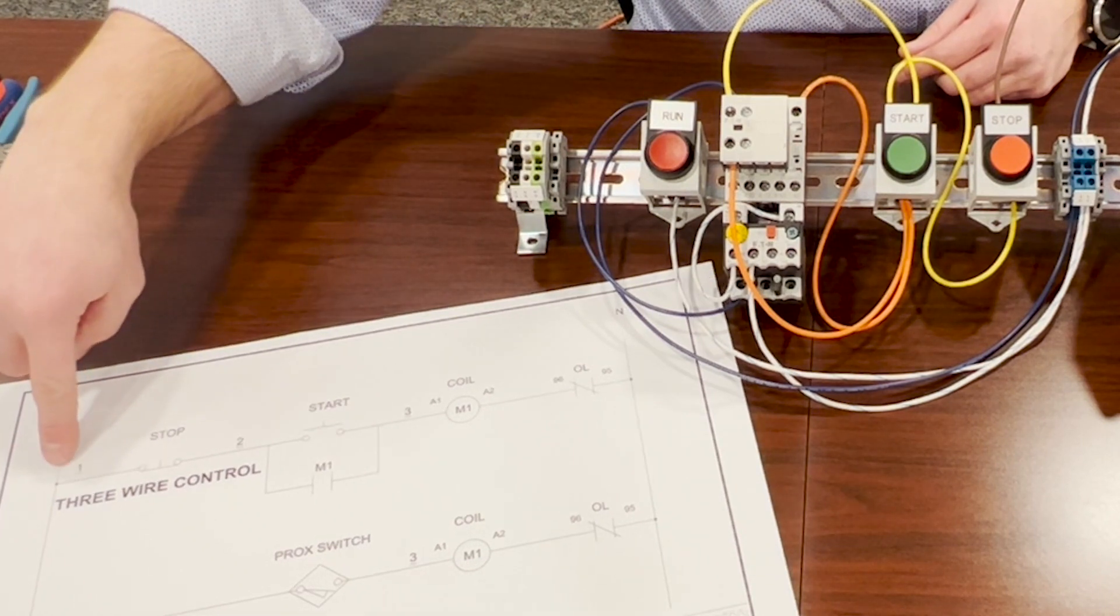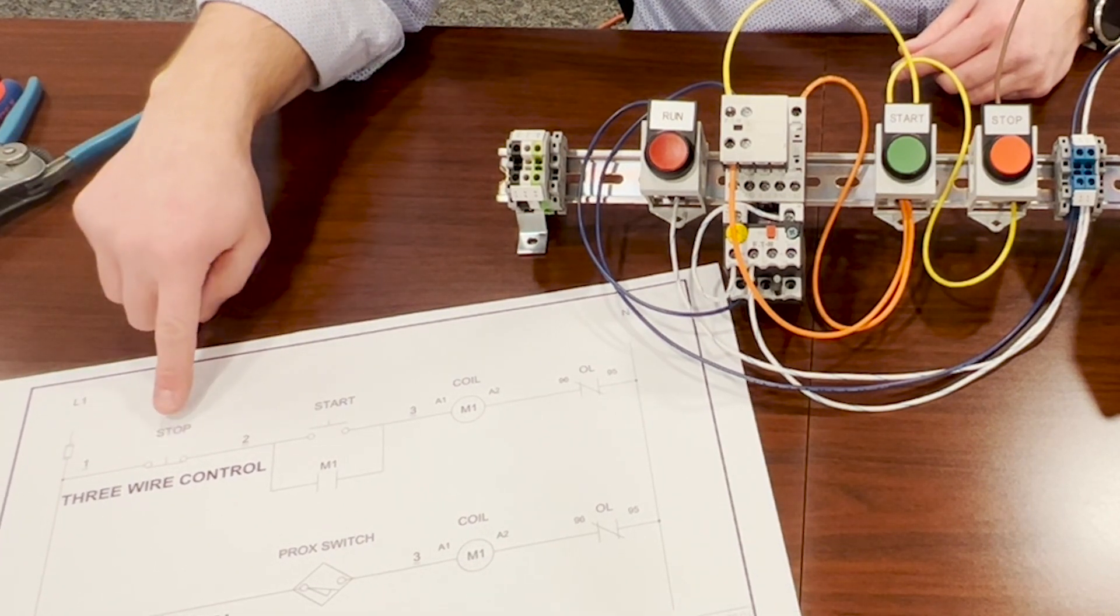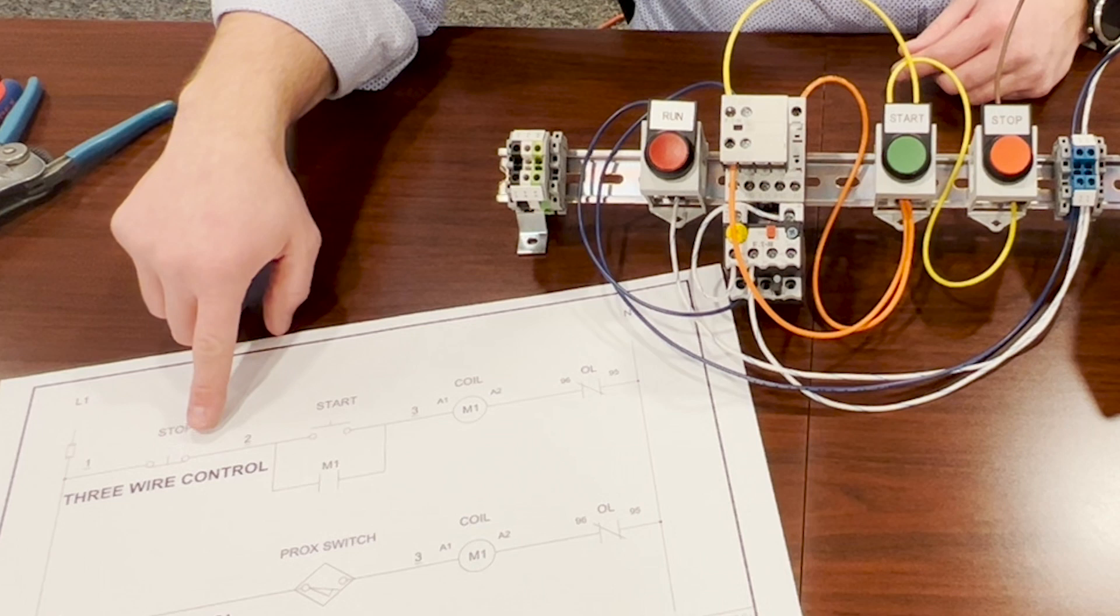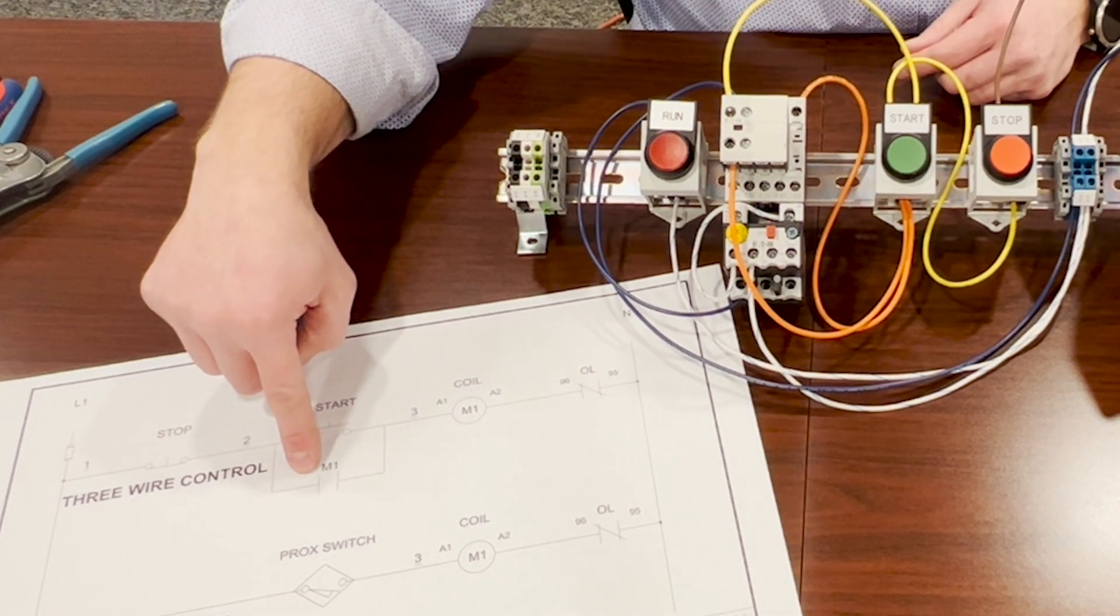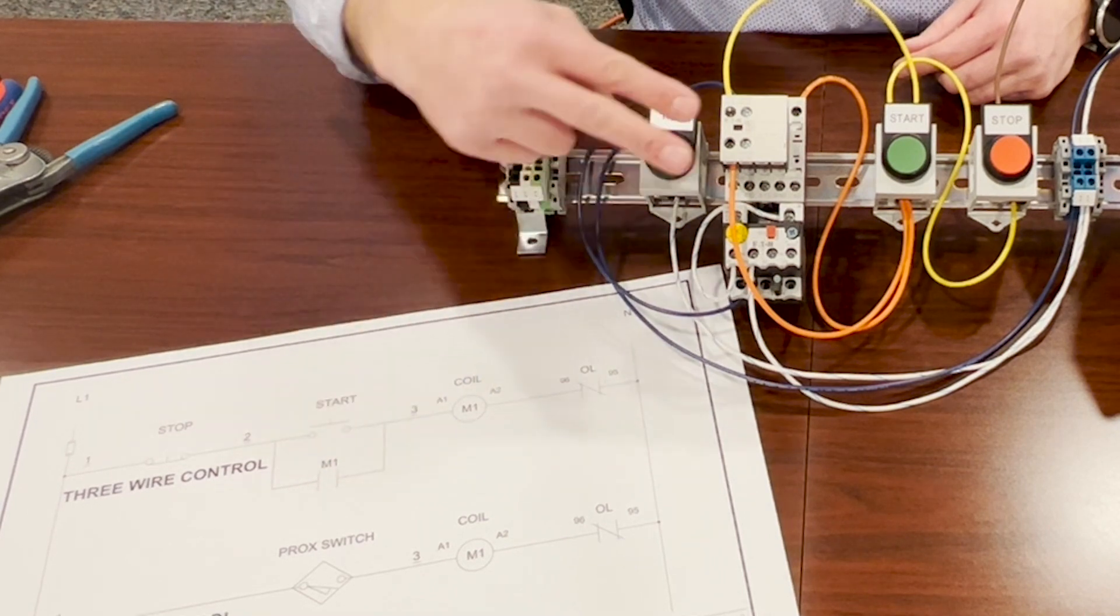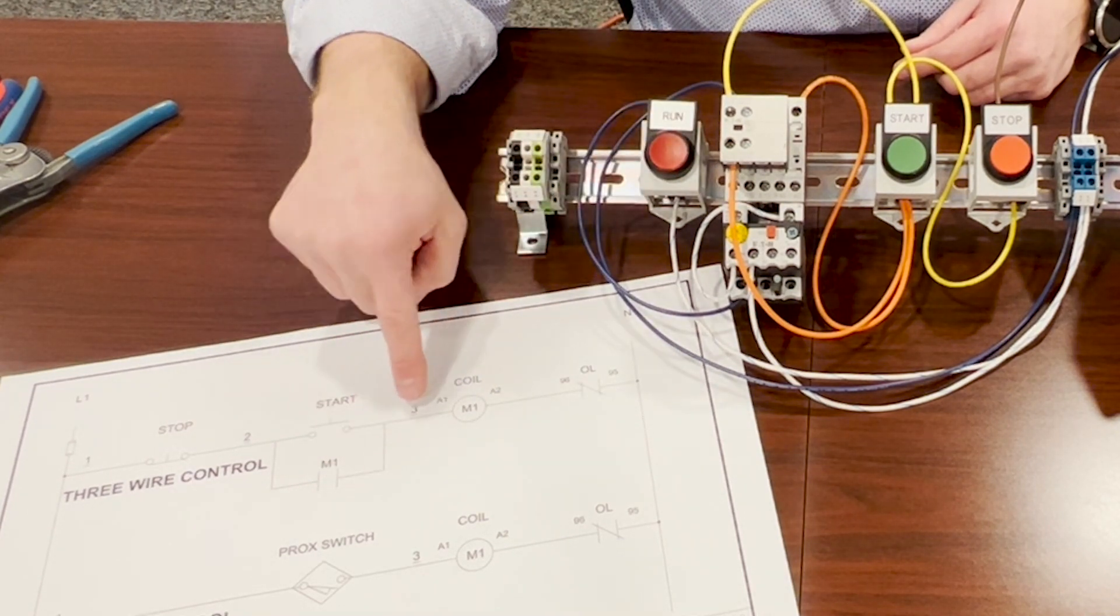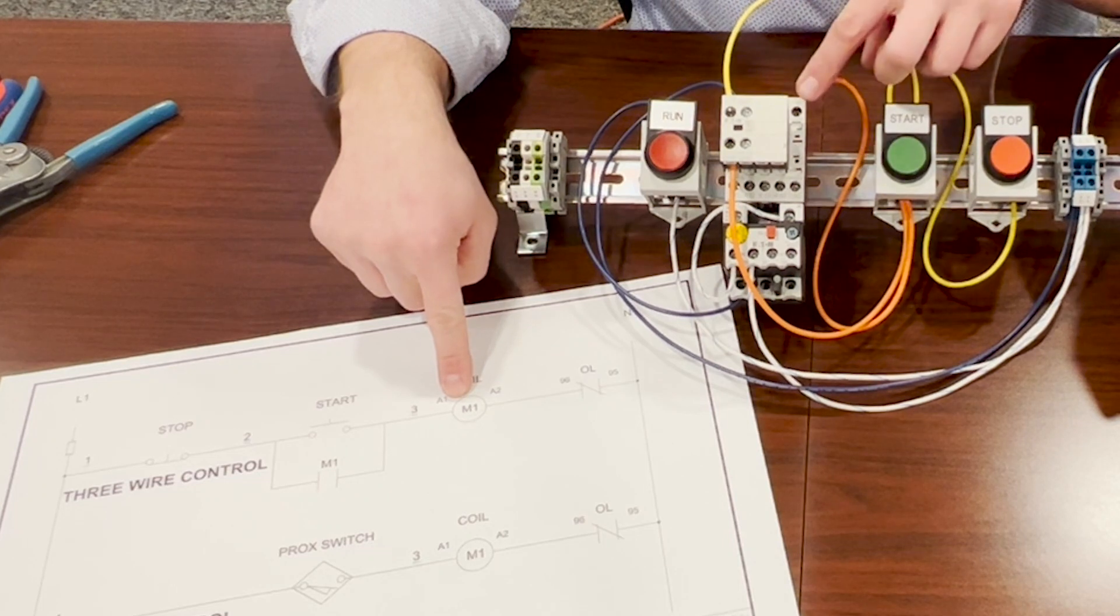So 24 volts to the normally closed on the stop button. From the stop button to the start, but also to the auxiliary contact on the motor starter, which is what we're showing here. And then from there, it's going to go to the coil on the starter here.